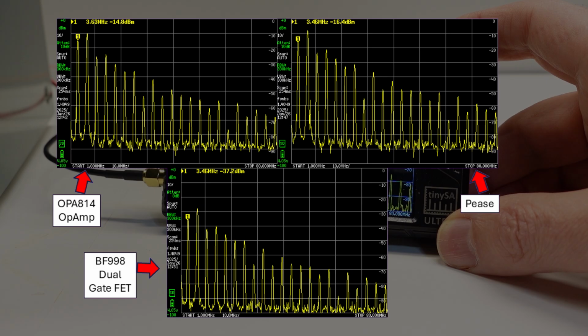Their frequency peaks follow the exact same up and down trend, and they're mostly within a couple of dB of each other. The dual gate FET is also showing equivalently useful information, but of course its peaks are about 20 dB lower than the other 2 probes because of the probe's inherent attenuation. Now this is a broad frequency sweep at a 300 kHz resolution bandwidth, so don't slice and dice the absolute magnitude of each peak. Doing that would take several narrower frequency sweeps at a much lower resolution bandwidth, and likely would need a better instrument than my TinySA.